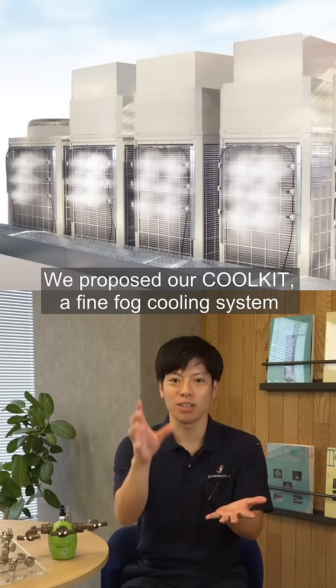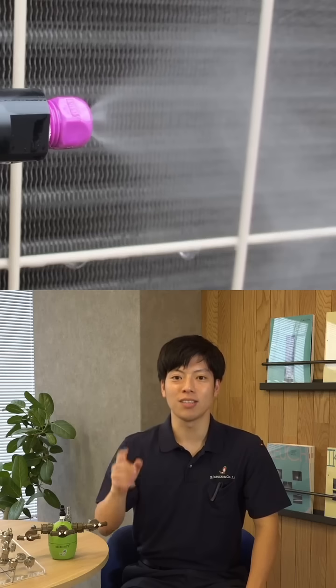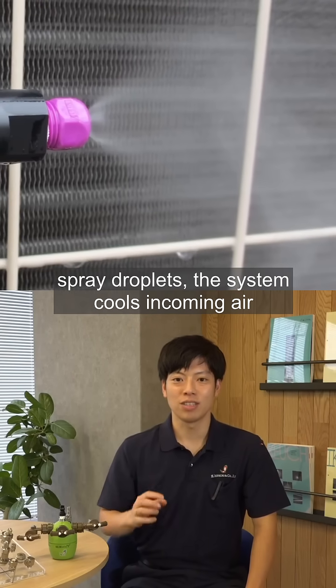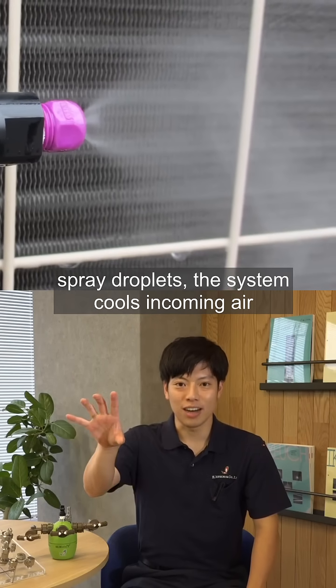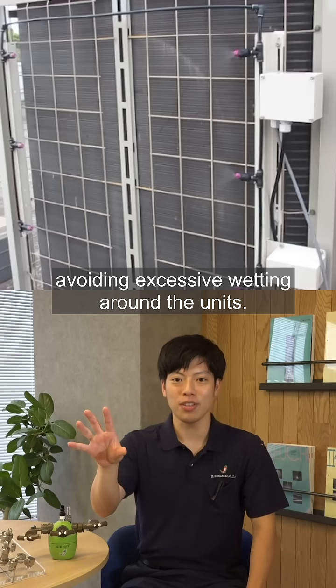We proposed our COOLKIT, a fine fog cooling system installed at the air intakes of outdoor units. By using the heat of vaporization from ultra-fine spray droplets, the system cools incoming air efficiently while minimizing water consumption and avoiding excessive wetting around the units.